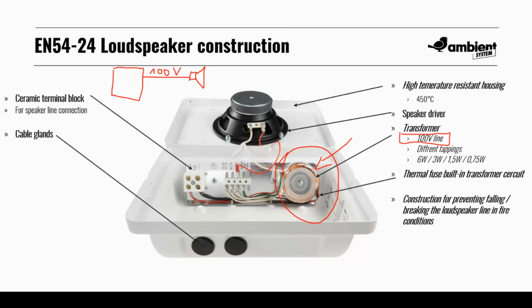And why do we do this? That is because in the voice alarm installation, we usually have a large number of speakers, and these speakers must be connected, in many cases, to the same line. Now, if we do this with our home theater speakers, we will overload the amplifier very quickly. That's why the 100-volt technique has been introduced to voice alarm and public address, to be able to drive multiple speakers connected in parallel to one cable. We are just stepping up the voltage to be able to deliver the same power with less losses on the cable and with less influence on the amplifier load.